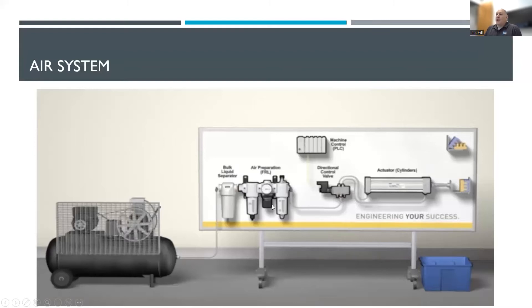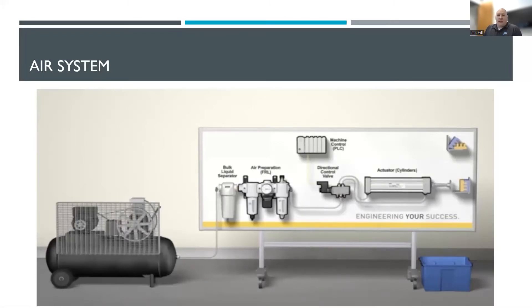There are a lot of elements on the front end of the system, but you might also place air prep at a machine level or closer to where the work is actually being done. That depends on what you're using to do that work — some actuators need a cleaner type of air. Typical filtration levels are 40 micron, 5 micron, and 0.1 micron, so you can get down to extremely clean air for clean-room applications like chip manufacturing. When you need ultra-clean air, you step down through a series of filters rather than just one super-fine filter, which would plug up all the time.